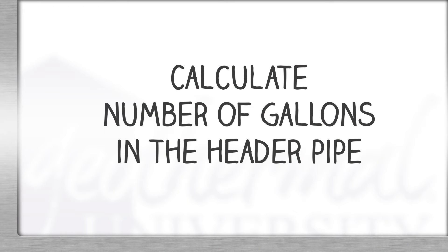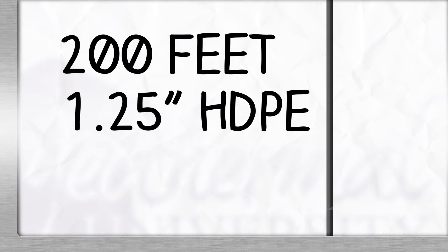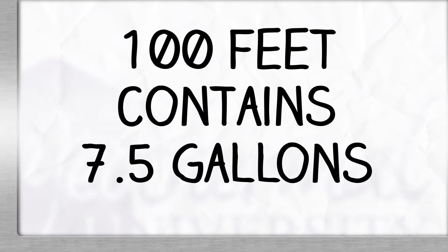Next, we'll need to calculate the number of gallons in the header pipes. In our example, our header pipe consists of 200 feet of inch and a quarter HDPE pipe. Using Table 4 in our Flow Center and Loop Application Installation Guide provided with this video, we scroll down to inch and a quarter size dimension ratio 11 or SDR 11, and we find 100 feet contains 7.5 gallons.